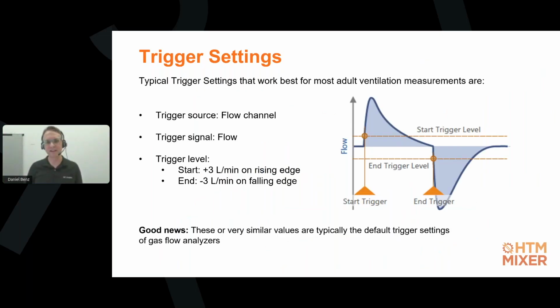So this is why the flow signal in the flow channel, with a start trigger level that is a low positive number on a rising edge and a stop trigger at a low negative number on a falling edge of the signal, typically works perfectly fine. And this is also why these settings you can see here on the slides, or very similar ones, are typically the default trigger settings of your gas flow analyzers. All of them have pretty much the same settings as default settings. That's most likely why you have never had to touch them.